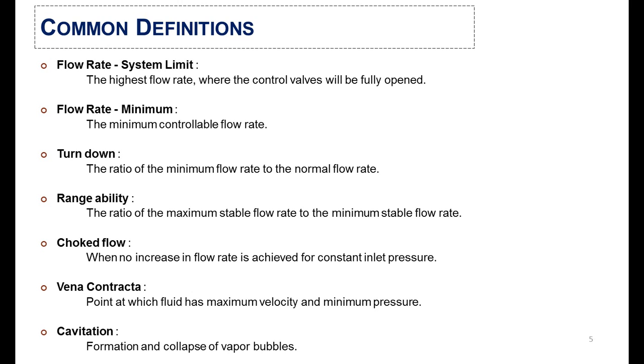The fourth definition is rangeability: it is the ratio of maximum stable flow rate to the minimum stable flow rate. The next definition is choked flow — dead flow — when there is no increase in the flow rate with constant inlet pressure. The second-to-last definition is vena contracta: the point where the velocity is maximum and pressure is minimum. The last definition is cavitation, which is the formation and collapse of vapor bubbles.